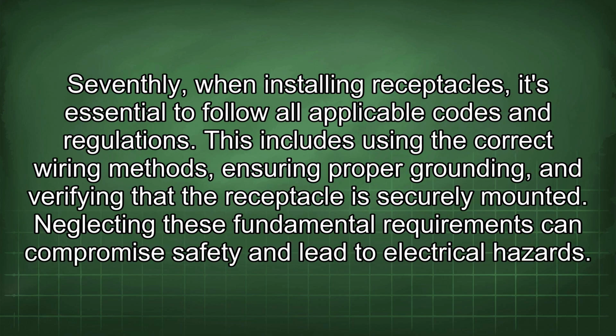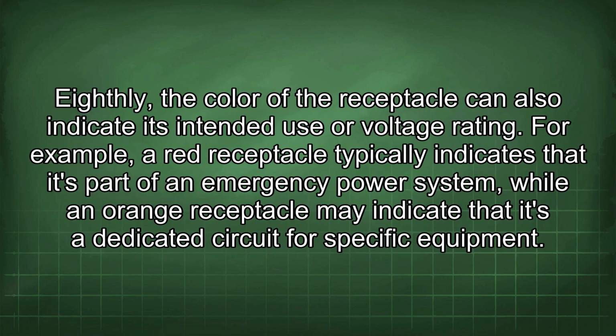Seventhly, when installing receptacles, it's essential to follow all applicable codes and regulations. This includes using the correct wiring methods, ensuring proper grounding, and verifying that the receptacle is securely mounted. Neglecting these fundamental requirements can compromise safety and lead to electrical hazards. Eighthly, the color of the receptacle can also indicate its intended use or voltage rating. For example, a red receptacle typically indicates that it's part of an emergency power system, while an orange receptacle may indicate that it's a dedicated circuit for specific equipment.